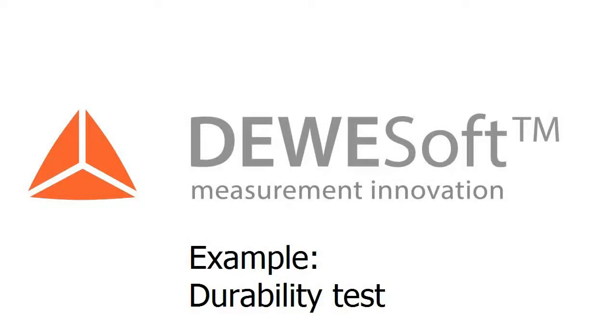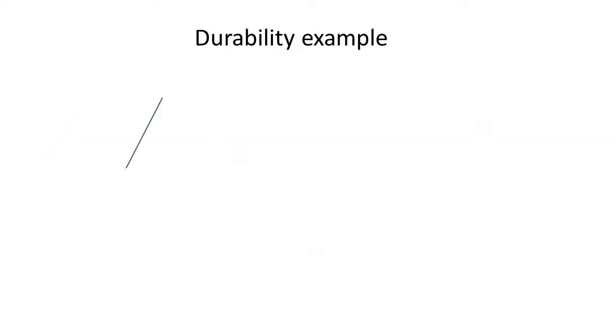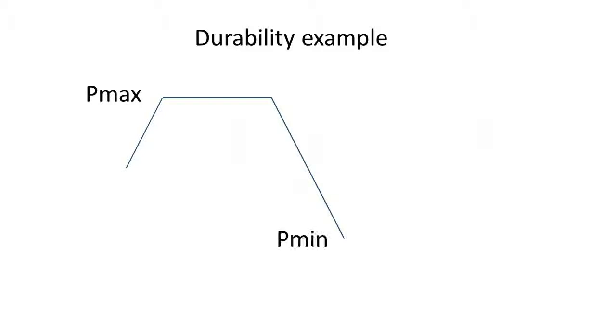One of the major applications is the durability test. We want to inflate the balloon until P max, hold the pressure for a certain time, deflate to P min, hold and inflate again. This we repeat thousand times.